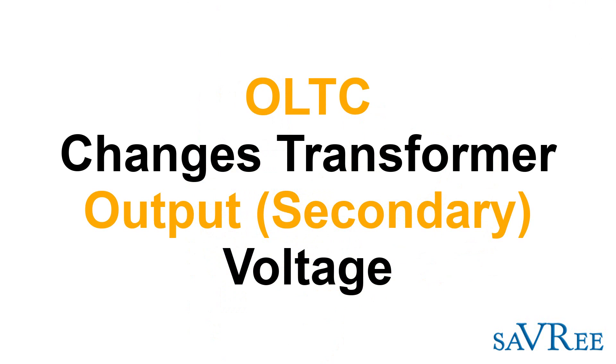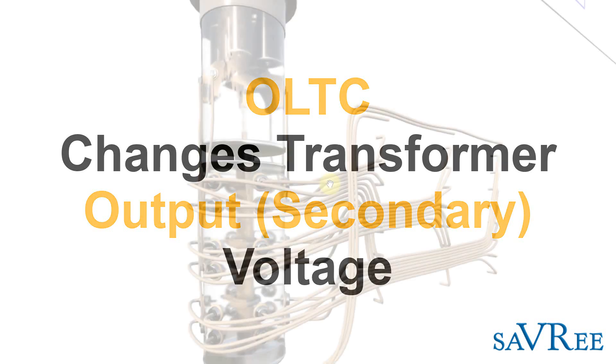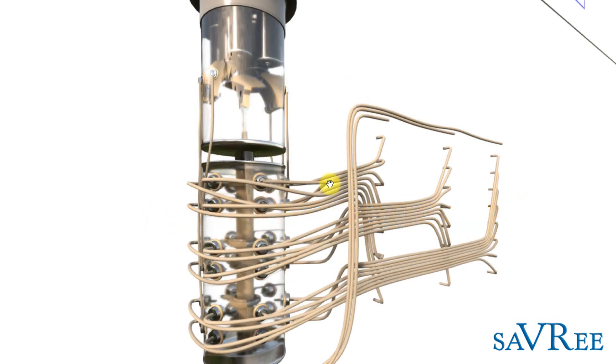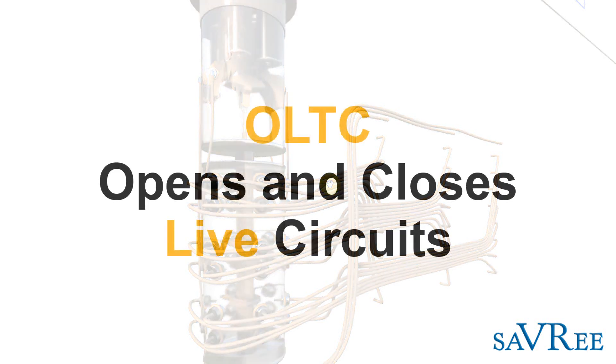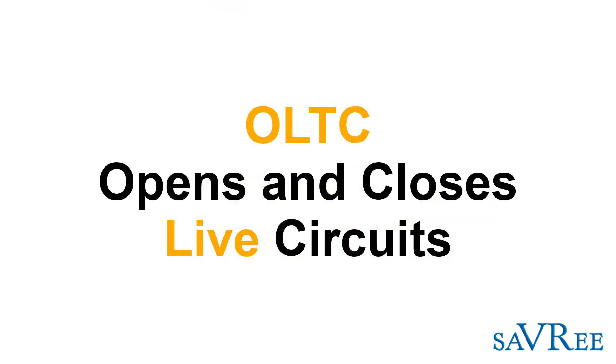That's all the tap changer's doing. Because the tap changer is an on-load tap changer, doing this is not particularly easy. Changing the number of turns on a secondary winding when you're operating at 110,000 volts or potentially more is actually quite difficult. So we need to be able to do this when the transformer is online, and that means we need to break and close the circuit without interrupting it or causing it to trip.